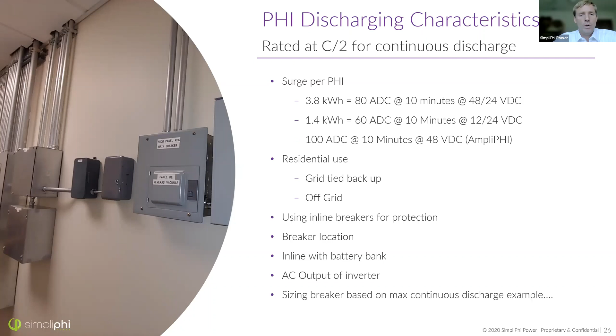Can you do that? Yes, you definitely cannot rely on our internal breakers, because our internal breakers are sized for a surge. Right? And there's nothing that would make those breakers go off at 37.5 amps per battery, right? They're capable of surging up to 80 or 100 amps. So if you installed inline breakers, the problem with this is that these breakers have a lot of variation in how they respond. So I will get into that a little bit.